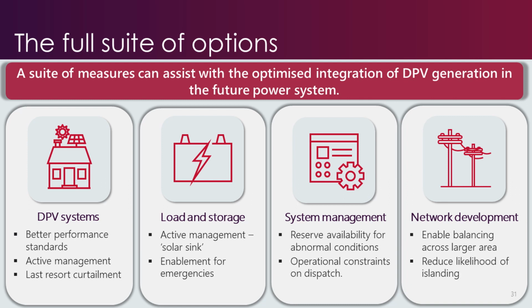Next, we have balancing DPV generation with load and storage in the distribution network and behind the meter, essentially introducing sources of demand to soak up excess DPV generation in the day. This undoubtedly will play a massive role into the future. However, this source of flexibility is not at sufficient levels today to address the key bulk system DPV integration challenges we're concerned about, especially during extreme abnormal system conditions. Next, we have system management solutions, which cover procurement of reserves to better manage the risks associated with mass DPV disconnection and operating the system more conservatively to reduce or eliminate the chance of getting into high risk or inoperable system conditions.